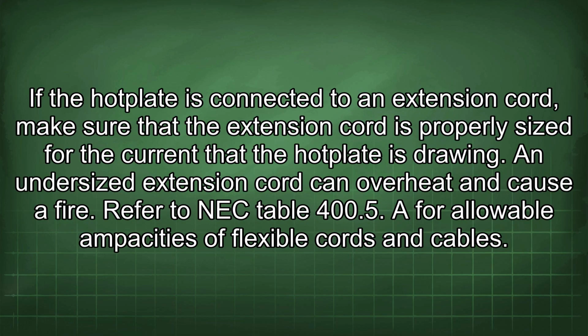If the hotplate is connected to an extension cord, make sure that the extension cord is properly sized for the current that the hotplate is drawing. An undersized extension cord can overheat and cause a fire. Refer to NEC Table 400.5 for allowable ampacities of flexible cords and cables.